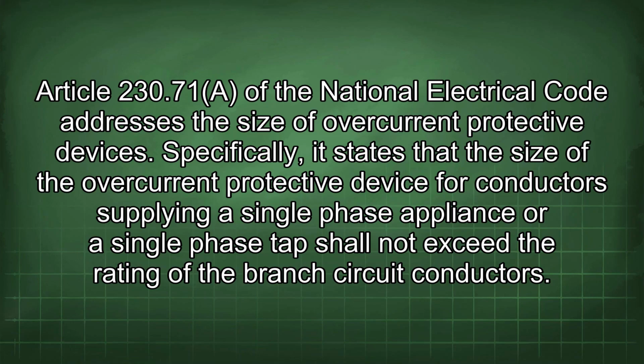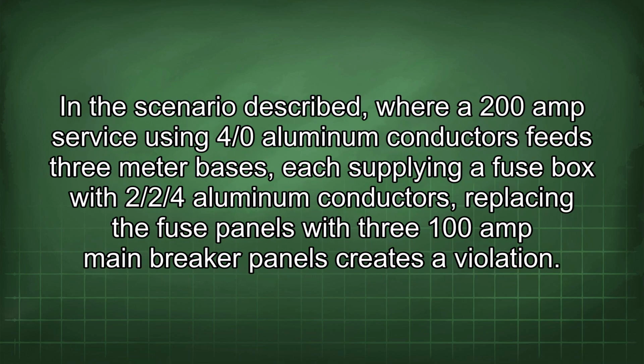Article 230.71 of the National Electrical Code addresses the size of overcurrent protective devices. Specifically, it states that the size of the overcurrent protective device for conductors supplying a single-phase appliance or a single-phase tap shall not exceed the rating of the branch circuit conductors. In the scenario described, where a 200 amp service using 4/0 aluminum conductors feeds 3 meter bases, each supplying a fuse box with 2/2/4 aluminum conductors, replacing the fuse panels with 3 100 amp main breaker panels creates a violation.